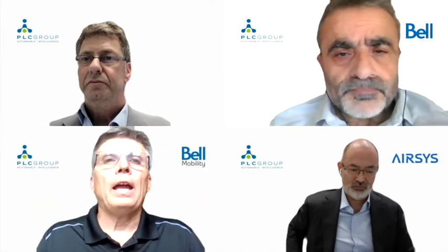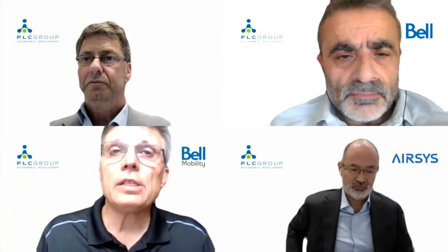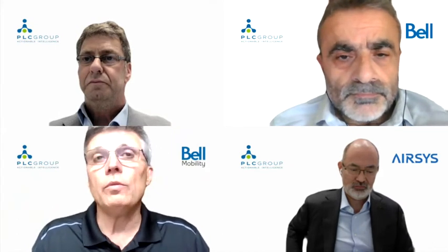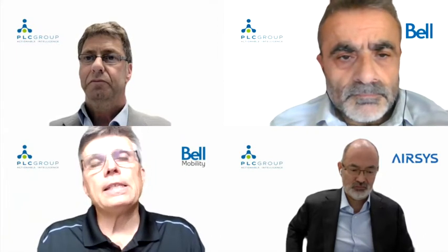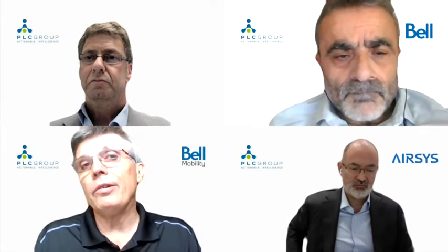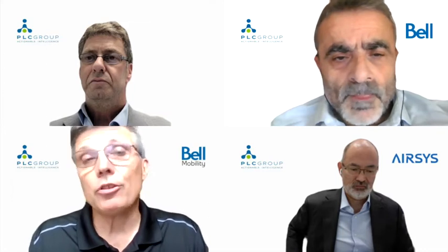This is not human comfort, this is equipment comfort, and most of the equipment I deal with has tolerances up to 40 degrees Celsius or beyond. Power plants, 55 degrees Celsius. A lot of the BBUs and radio equipment we use are also 55-degree rated with no reductions in performance. So the most sensitive box in a cell site, for instance, would be the battery. A lead battery certainly doesn't want to live at 40 degrees and will be rather short-lived if you leave it there.